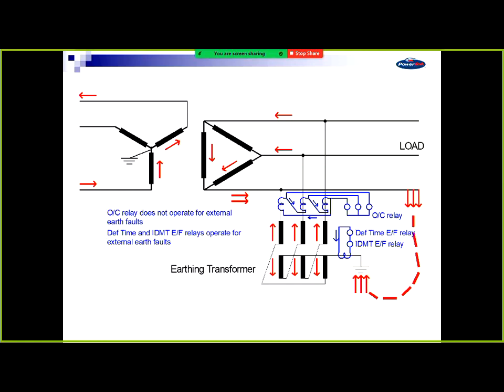The CT in the neutral leg is just sitting there, and that's doing a definite time and an IDMT earth fault. But the CTs are sitting in the phase currents, if we'll call it that. They're connected in delta. The reason for that is to trap the zero sequence current. So you see for that external earth fault current, there's no current flowing through the relay. So it doesn't matter how big that external fault is. What that gives us as an advantage is that we can set that overcurrent element really sensitive, and it only sees faults inside the earthing transformer. We said earlier that overcurrents can't be set sensitive. Well, this one can be, because of the way we connected it up and because there's only zero sequence current flowing for external faults. You won't get phase current. You won't get any positive or negative sequence current out of your earthing transformer. You only purely get the zero sequence current.